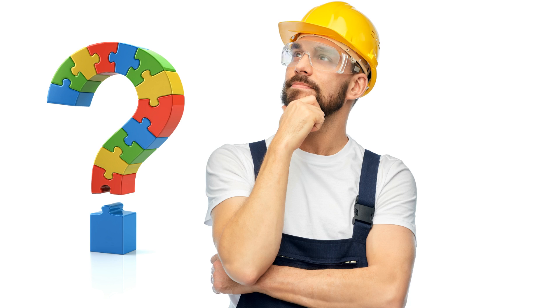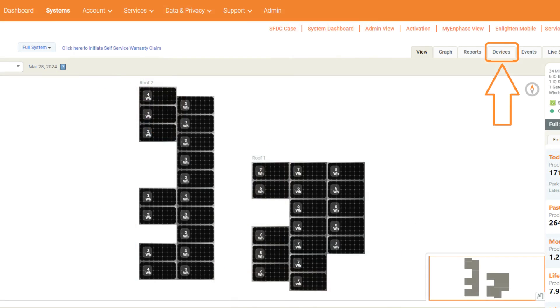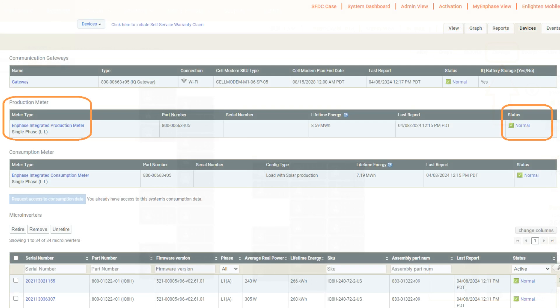As an example, disabled or misinstalled production meters will cause insufficient data to report. To view and change meter configuration, log into the Enphase installer portal and open the relevant site. Click the Devices tab in the gray taskbar. Scroll to Production Meter and check the status section. It should display as normal.